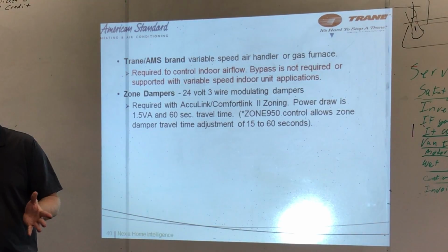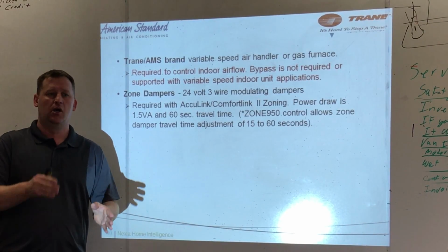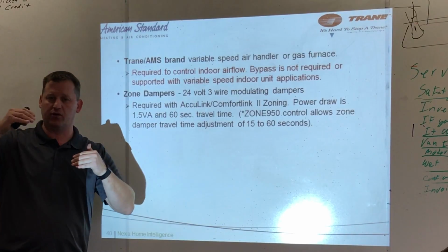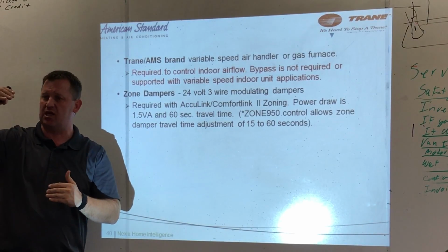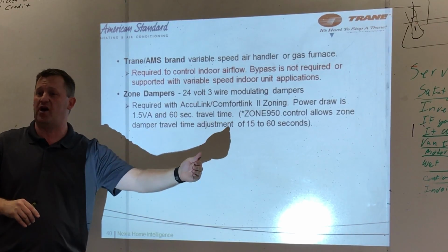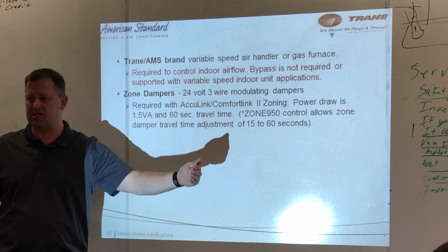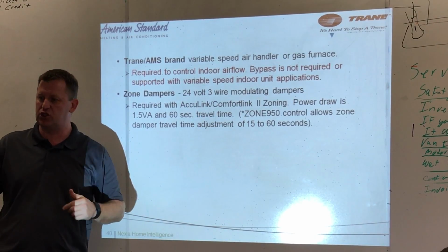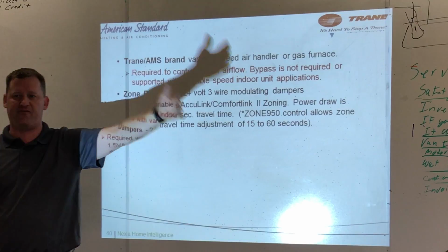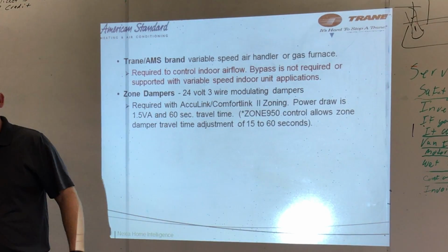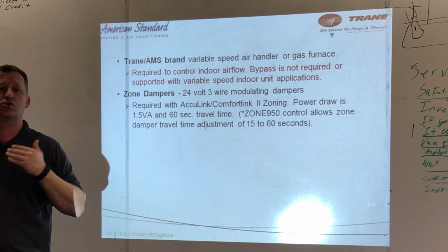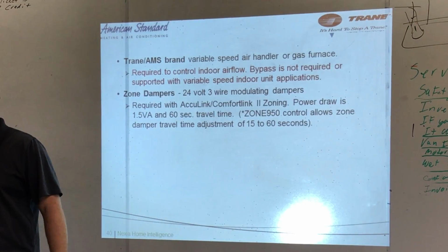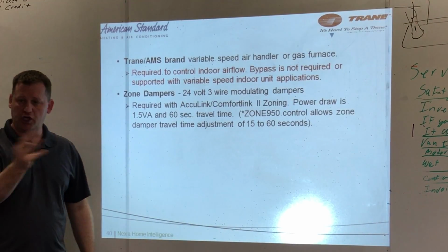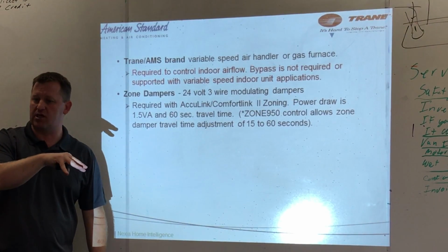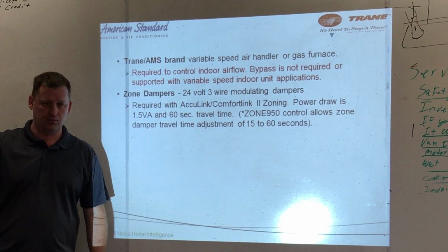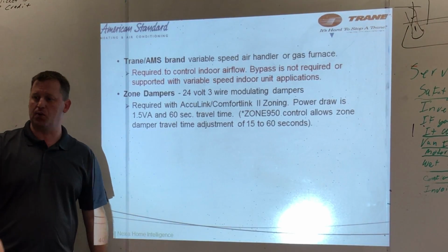EWC is the company building our dampers for us. Even though their dampers look almost exactly the same, their damper timing is 35 seconds. Ours are 60 seconds. I ran into a situation in Horseshoe Bend where they had half of the dampers Trane, half the dampers EWC, and they had all sorts of weird things and an unhappy homeowner. Okay? We changed all the dampers over to the 60-second travel time. Problems went away. We had to change some damper motors. Okay?